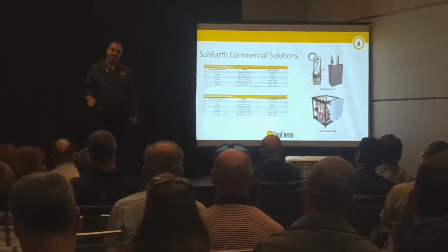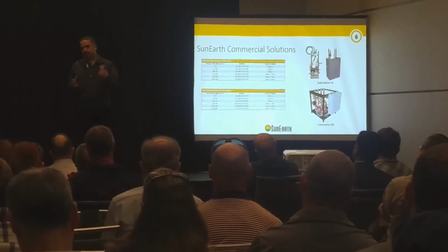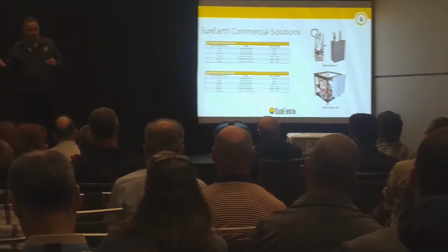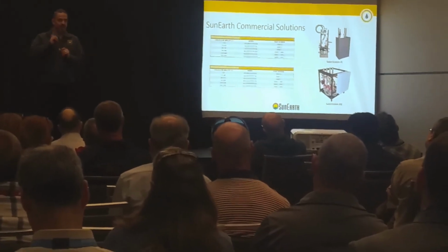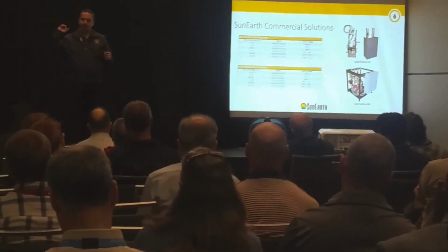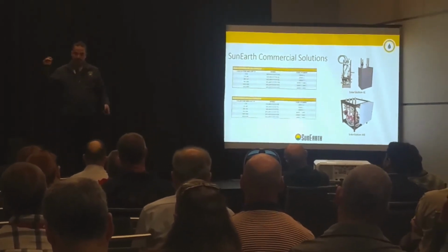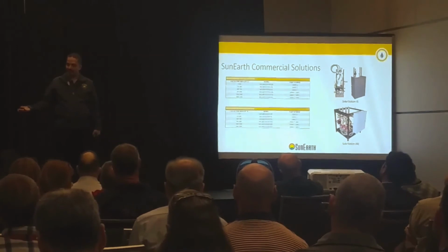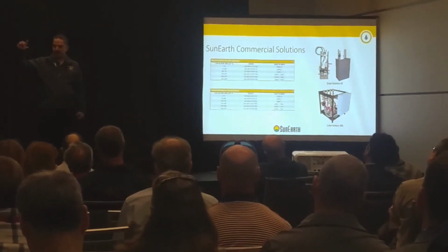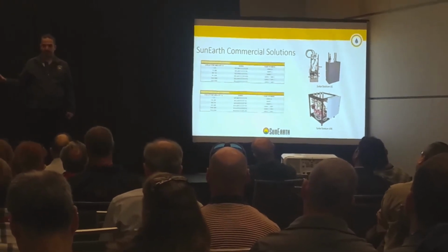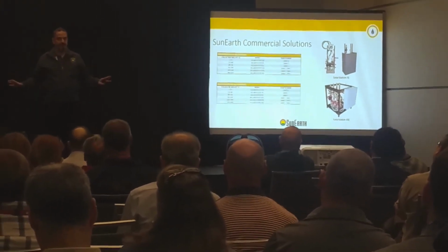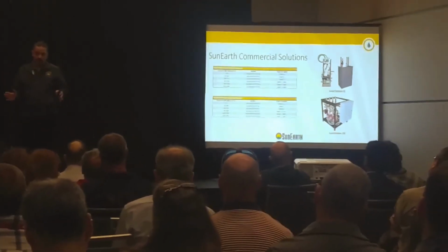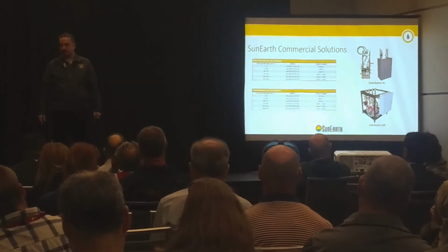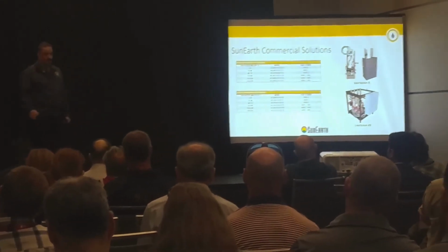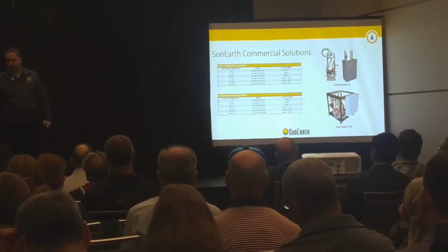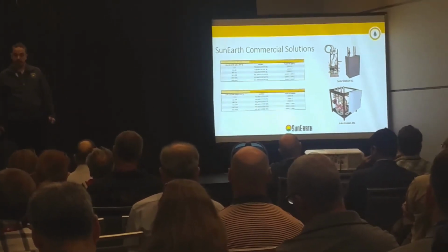Very simple: heat injection. So let's say you have a 3-inch line to your boiler. We will inject heat constantly via a 1-inch standard line into that 3-inch line. There's no pressure drop, and by preheating the water feeding into your boiler, we take the same load off without messing with your pressure drops or system flow. It's very simple, very reliable, and has been deployed in the field for the past 3-4 years with huge success. That's another factor we're looking at to bring down the general initial cost of investment for solar thermal commercial installations.